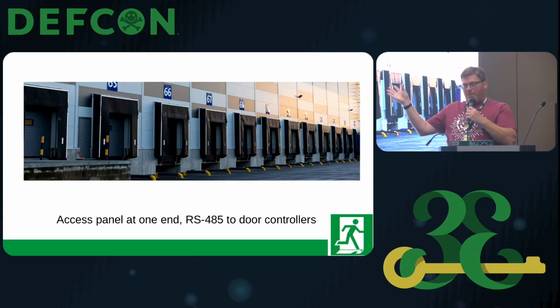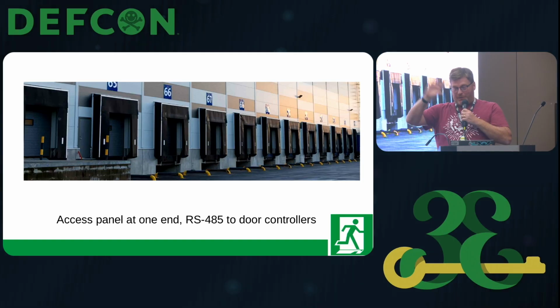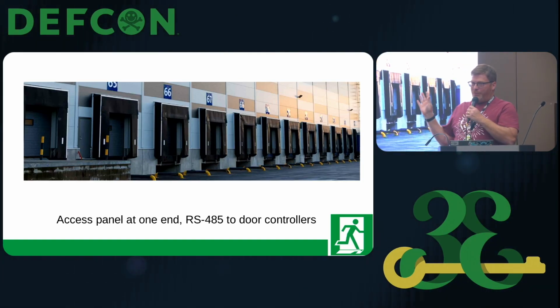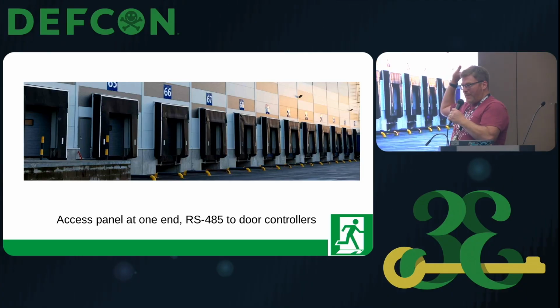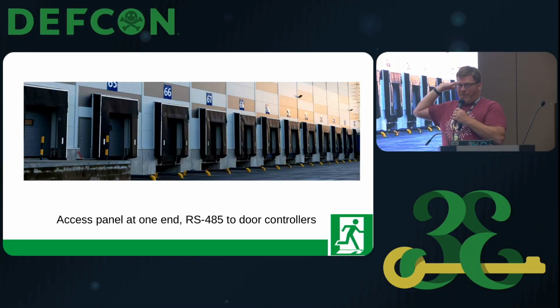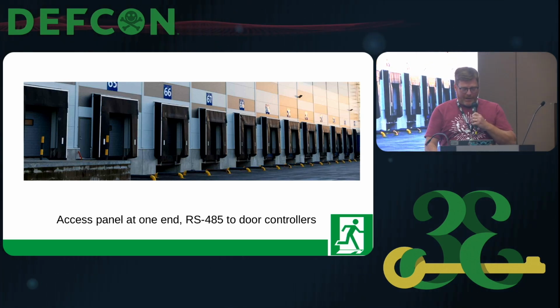The wiring's exposed, there's no EMI, no rats up there, so it's easy to troubleshoot and figure out. In that case, rather than trying to do Ethernet to all of these with fiber media converters to reach 800 or 1,000 feet, you just do a single run of RS-485.